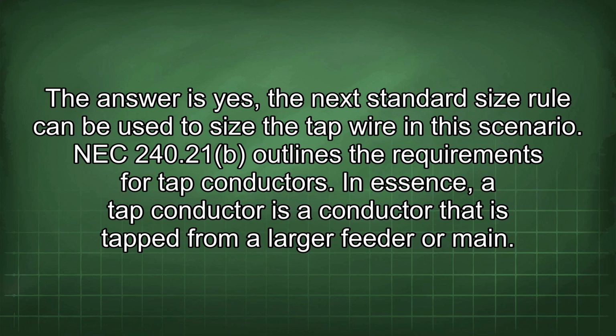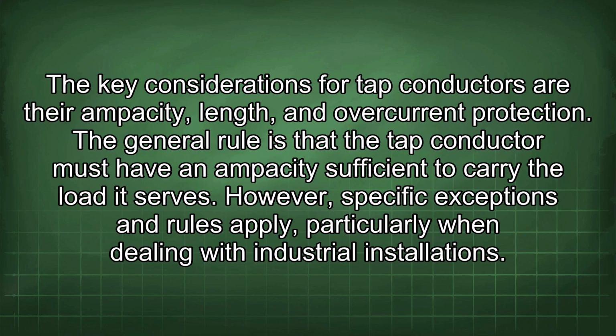NEC 240.21 outlines the requirements for tap conductors. In essence, a tap conductor is a conductor that is tapped from a larger feeder or main. The key considerations for tap conductors are their ampacity, length, and overcurrent protection. The general rule is that the tap conductor must have an ampacity sufficient to carry the load it serves. However, specific exceptions and rules apply, particularly when dealing with industrial installations.